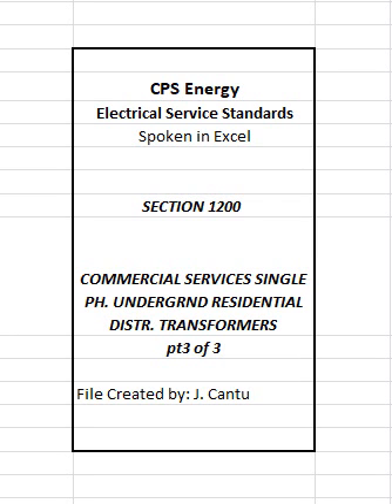B. Slab requirements. Compartment-type transformers sized at 250 kVA and greater will require the customer to construct a custom slab in accordance with CPS Energy specifications provided by the customer service representative. The provisions of 1 through 5 below will be applicable for installation of transformer and/or pull box slabs. 1. The top of the slab shall be a minimum of 6 inches and a maximum of 12 inches above final grade. 2. There shall be no pipes, conduits, etc. under the slab except those necessary to supply primary to the transformer and those required to supply the electric load.